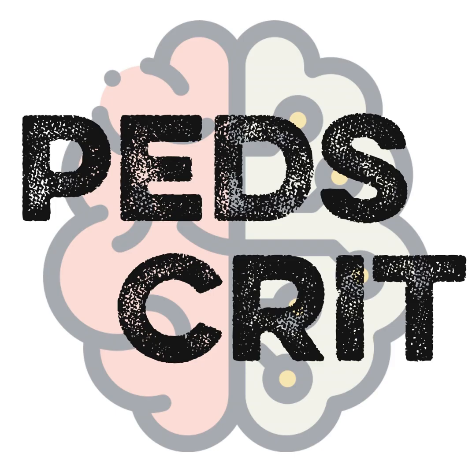You don't have a respiratory rate or the level of volume or the level of pressure, except that you will set up backup ventilation, of course. So it's important. But usually the most important setting to set is the NAVA level. And the NAVA level, you should see that as a gain factor. It's the factor that will convert your diaphragmatic electrical activity into a pressure assist.